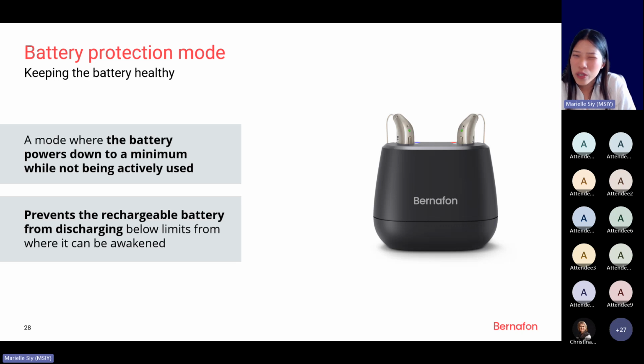And for those who are not really used to activating this battery protection mode, I really encourage that you start doing it. It's already available for Alpha and Alpha XT, and you can activate this again to keep the battery healthier for longer. Of course, as you know, this mode is where the rechargeable battery really powers down to the very minimum while it's not actively used. In this way, the rechargeable battery is prevented from discharging below the limit from where it can still wake up. So in short, the battery is not dead and you can still revive it if you activate this battery protection mode.